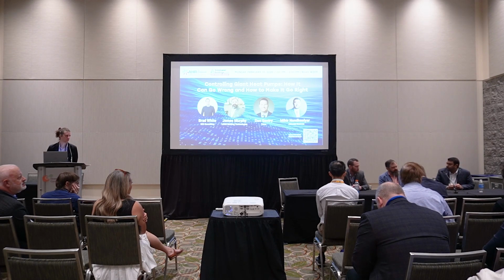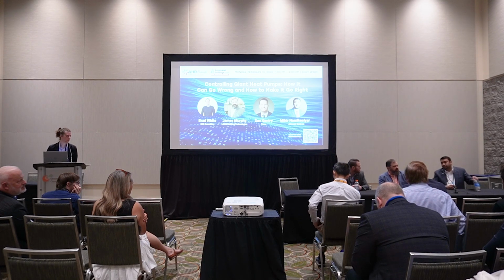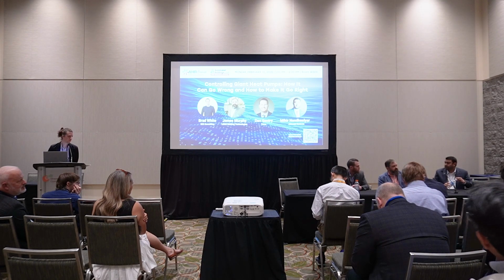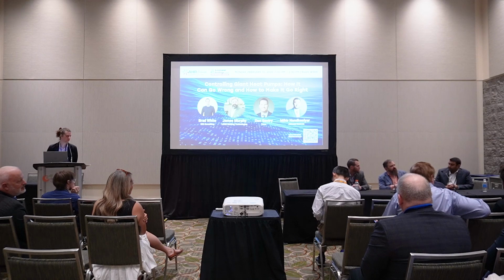And I think the other half of it we talked a little bit about earlier, which is volume, right? You can always solve a lot with more volume and, if it's heating, let your hot water set point kind of fall a bit, right? So maybe you don't need 120 degree water, maybe it's 100, maybe it's whatever, and you kind of let it drift off. And then when you kick it on, you raise it back up to 120. So you have that built-in load so that it can run with the volume. So you kind of have a bigger sine curve, if you will, on the load.